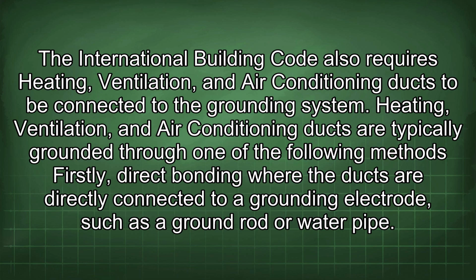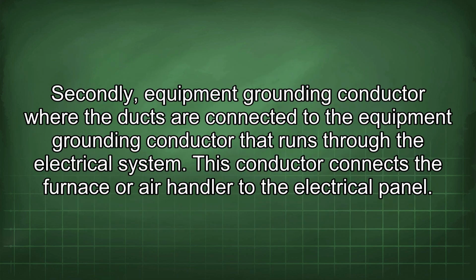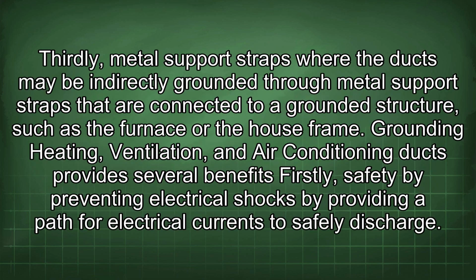Firstly, direct bonding, where the ducts are directly connected to a grounding electrode, such as a ground rod or water pipe. Secondly, equipment grounding conductor, where the ducts are connected to the equipment grounding conductor that runs through the electrical system. This conductor connects the furnace or air handler to the electrical panel. Thirdly, metal support straps, where the ducts may be indirectly grounded through metal support straps that are connected to a grounded structure, such as the furnace or the house frame.